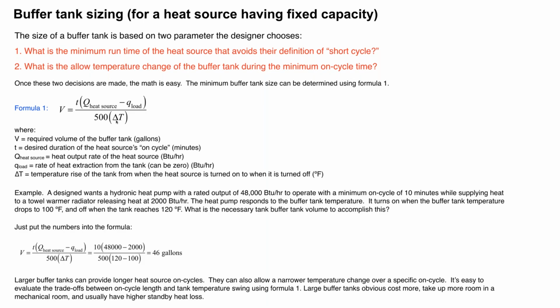Let's say a designer has a hydronic heat pump rated at 48,000 BTUs per hour. So it's a 4-ton heat pump, and we want it to run for 10 minutes. And let's say that during that time, we're going to have a towel warmer radiator releasing 2,000 BTUs per hour. The heat pump responds to the buffer tank temperature. It turns on when the buffer tank drops to 100 Fahrenheit, and then it turns off when the buffer tank gets up to 120. So there's our delta T between heat pump on and heat pump off of 20 degrees.